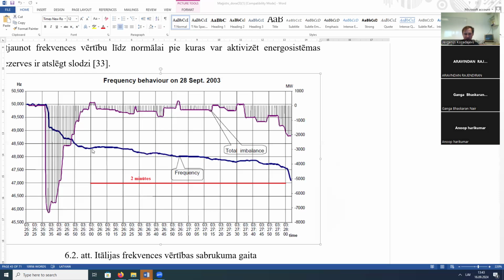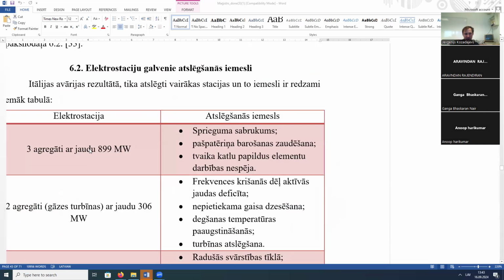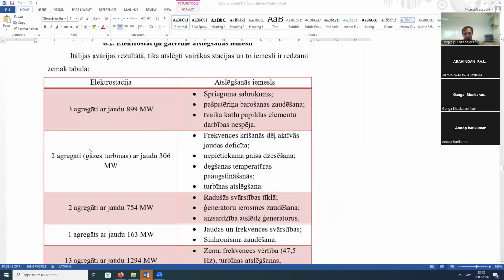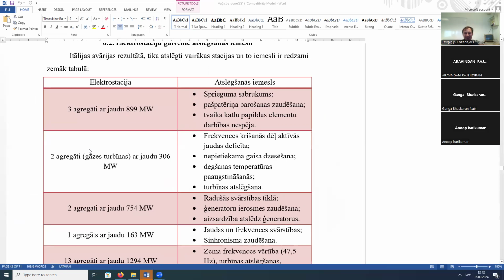So we remember we have time limits for almost all kinds of load and generation to operate with lower frequency. As a result, here we have a table with generator disconnection by the relay protection, because every generator is a very valuable and very expensive unit. It has its own protection, as I mentioned before, and the protection will disconnect the generator from the grid if we have any problems in the grid, to save the generator.